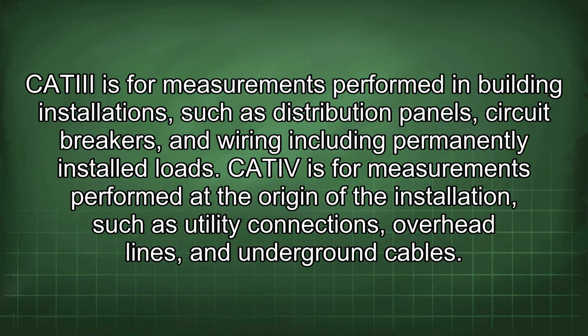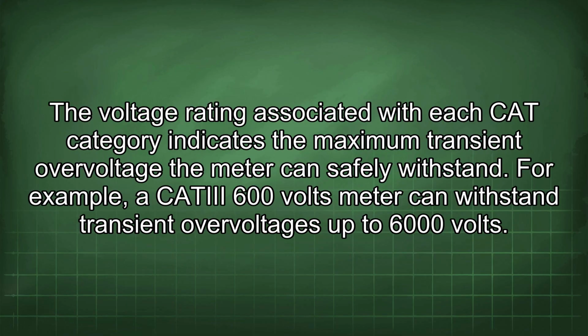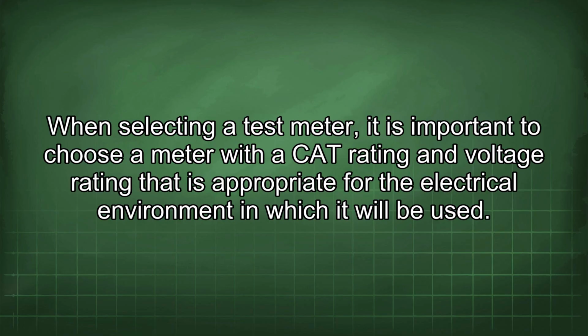CAT IV is for measurements performed at the origin of the installation, such as utility connections, overhead lines, and underground cables. The voltage rating associated with each CAT category indicates the maximum transient overvoltage the meter can safely withstand. For example, a CAT III 600 volts meter can withstand transient overvoltages up to 6000 volts. When selecting a test meter, it is important to choose a meter with a CAT rating and voltage rating that is appropriate for the electrical environment in which it will be used.